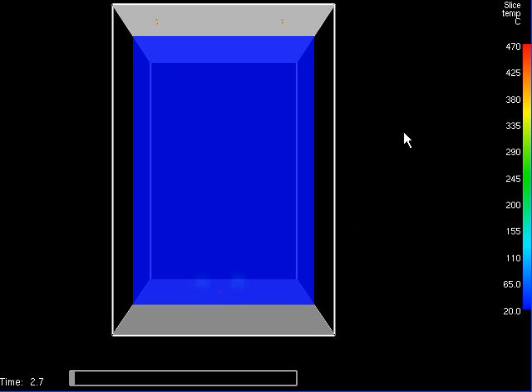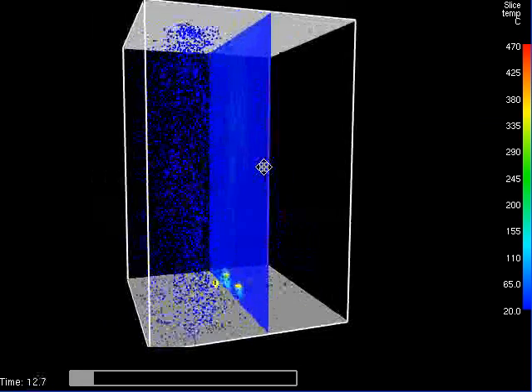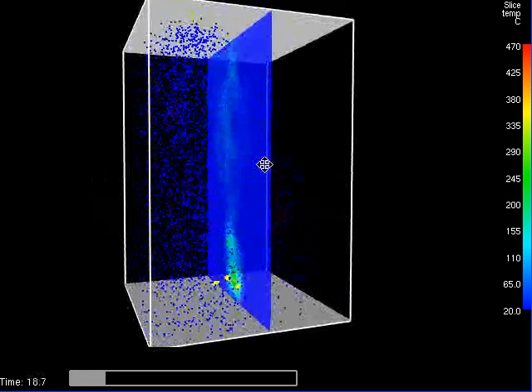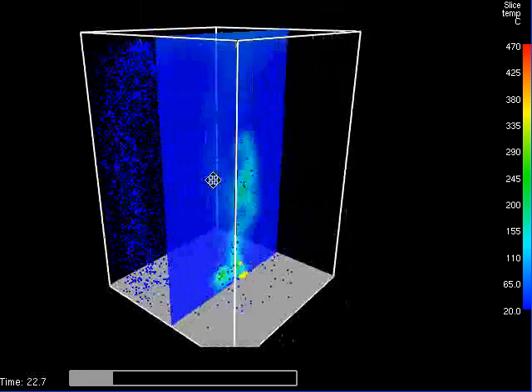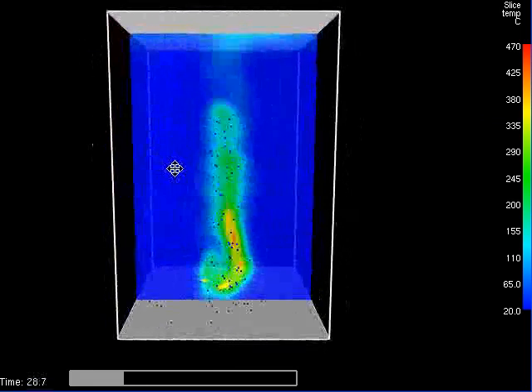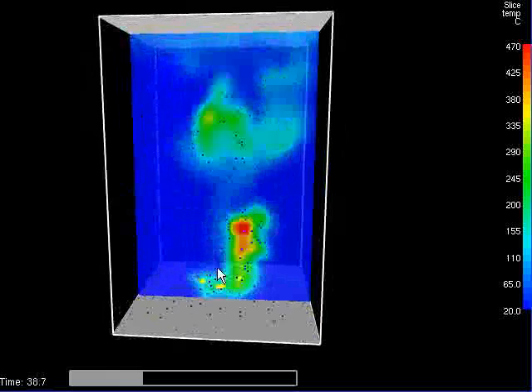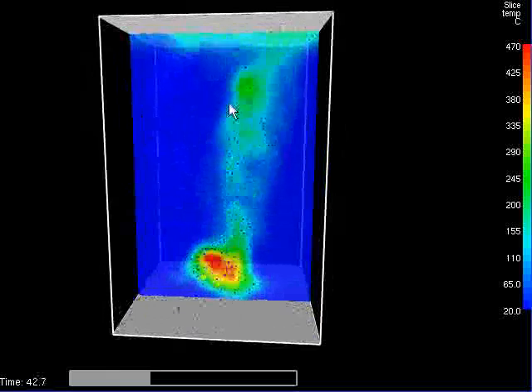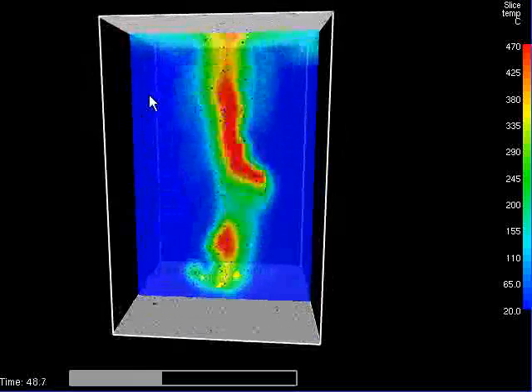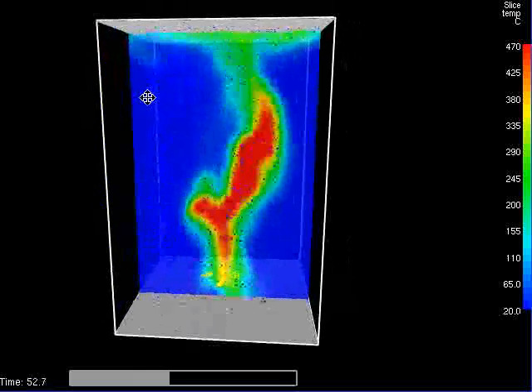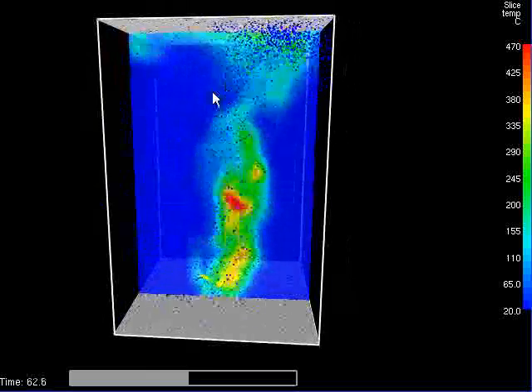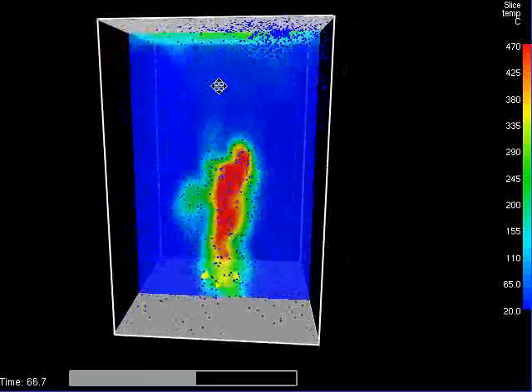So here you have, in the back left corner, a sprinkler that was set off manually after 5 seconds. You also see the gas phase temperatures in the y-plane. And you see that even with the sprinkler going off in the back left corner, at about 57 seconds the second sprinkler went off.